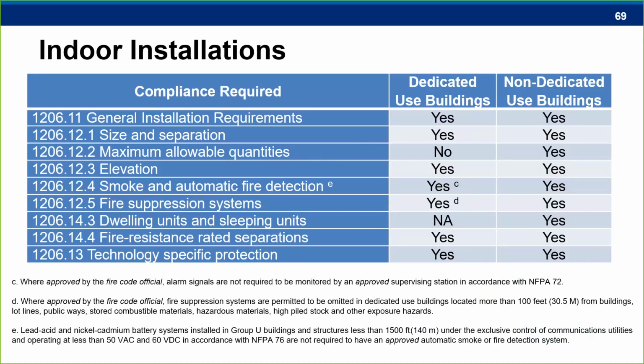And here, another chart. This is a list of the compliance that indoor installations need to meet. We already reviewed the general installation requirements, the electrochemical protections, and the chemistry-specific protection. There are two additional requirements that are needed for indoor installations that we'll review on the next slide. However, note on this slide that dedicated use buildings have some exceptions on the smoke and automatic fire detection and fire suppression system requirements. And that's because they pose a significantly less threat to life safety if an incident were to occur. So some of those requirements can be waived by the fire code officials.